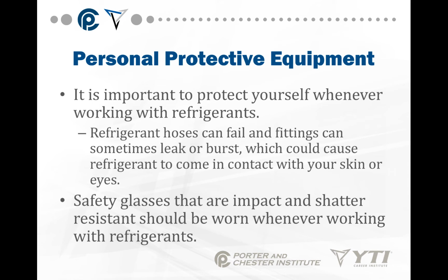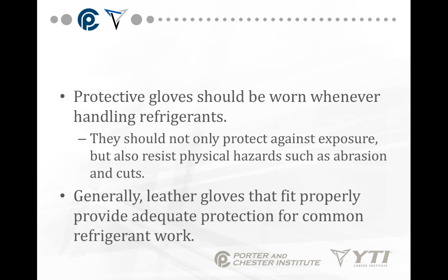Now, it's important to protect yourself whenever you're working with refrigerants. Refrigerant hoses can fail, and fittings can leak or burst, and that can cause refrigerants to come in contact with your skin or eyes. Safety glasses that are impact and shatter resistant should be worn whenever working with refrigerants. Protective gloves should be worn whenever handling refrigerants, and they should not only protect against exposure, but also resist physical hazards such as abrasion and cuts. Generally, leather gloves that fit properly provide adequate protection for common refrigerant work.